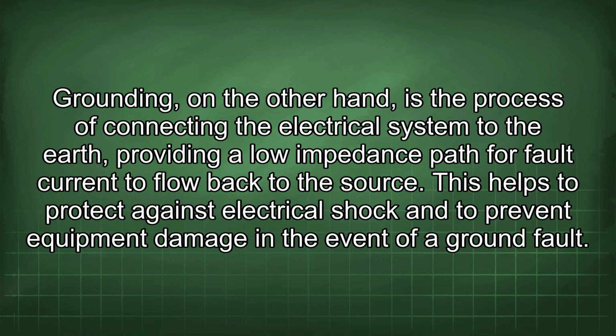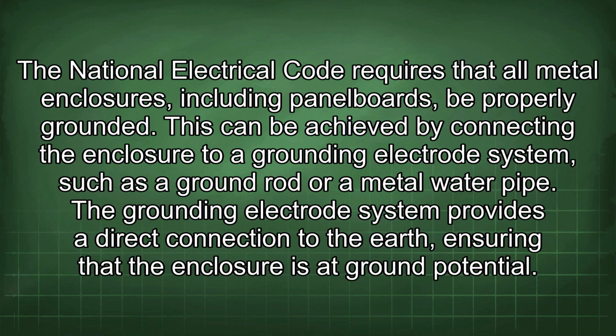Grounding, on the other hand, is the process of connecting the electrical system to the earth, providing a low impedance path for fault current to flow back to the source. This helps to protect against electrical shock and to prevent equipment damage in the event of a ground fault. The National Electrical Code requires that all metal enclosures, including panel boards, be properly grounded.